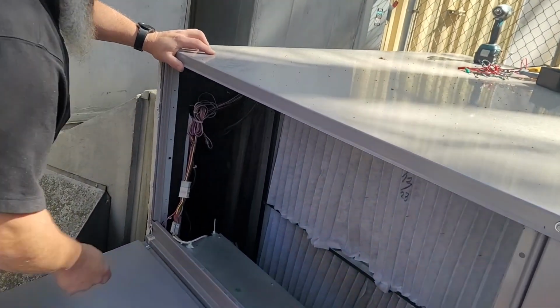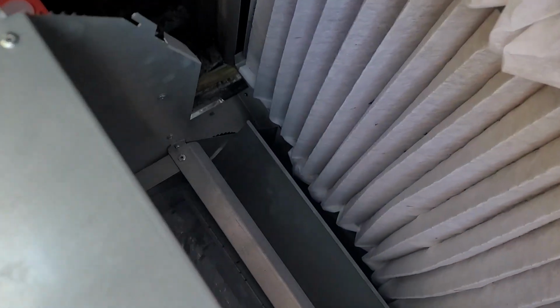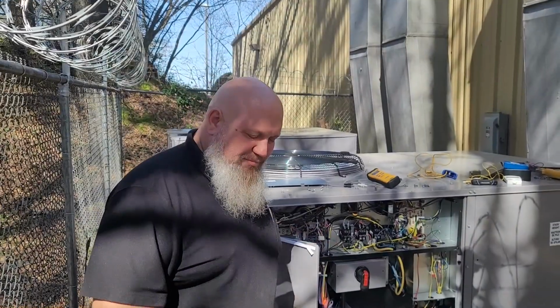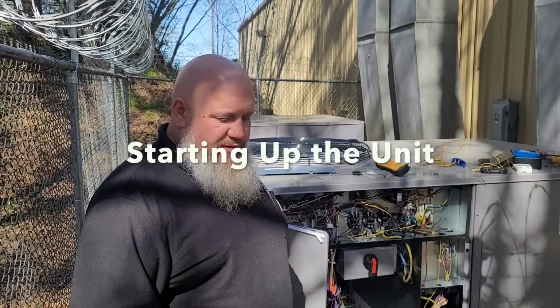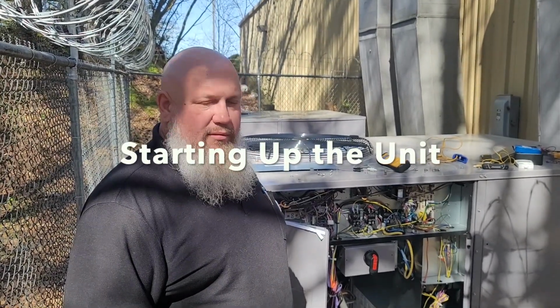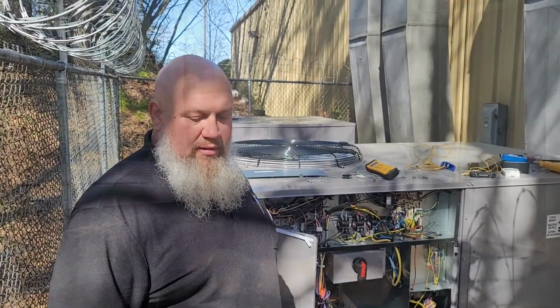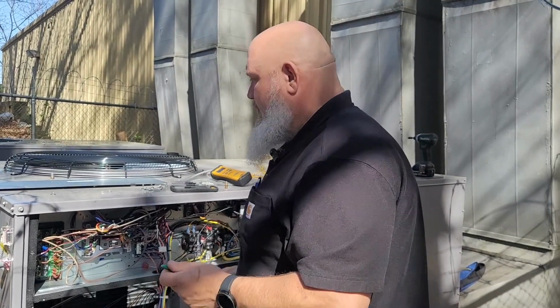First thing that catches my eye, there's a gap between the ductwork and the unit. That's why there's leaves on the filters. So that's something we need to address. Where are we at now on the form? We're about to start the unit up in cooling, bring it up to 100%. Can Mike tell us about this step?